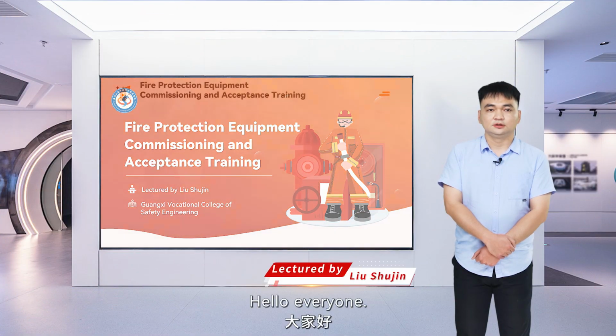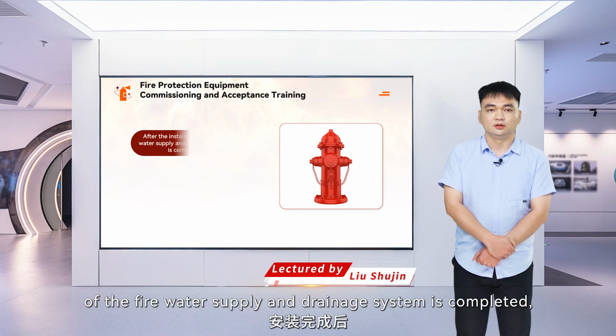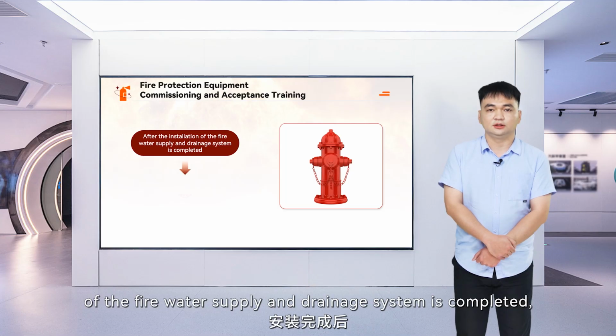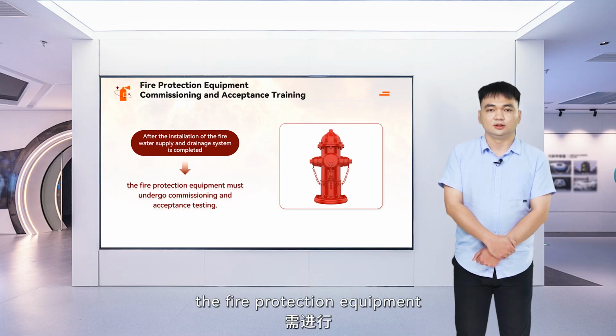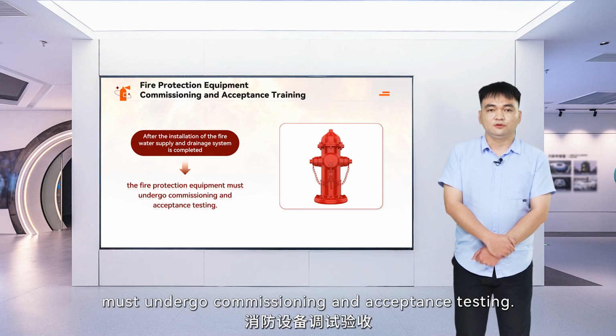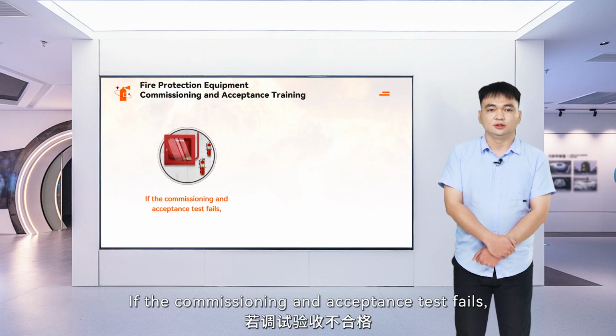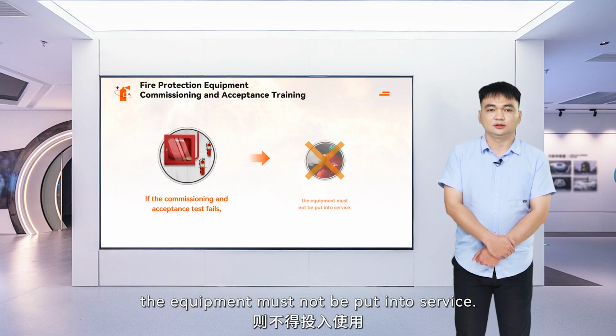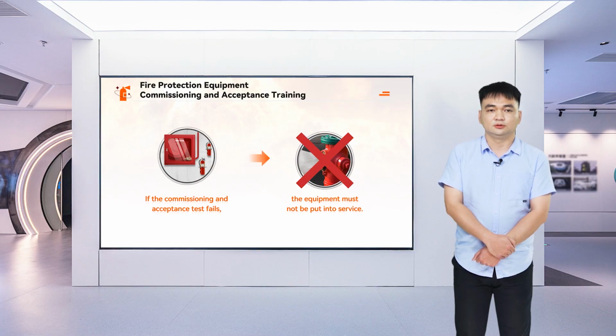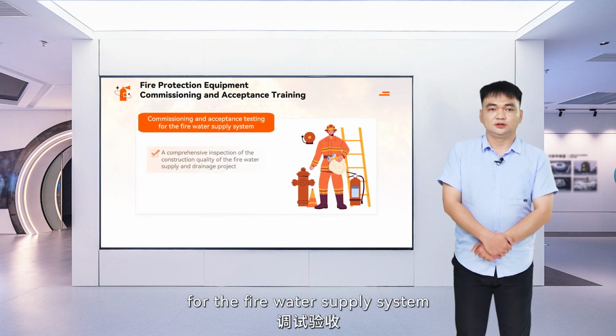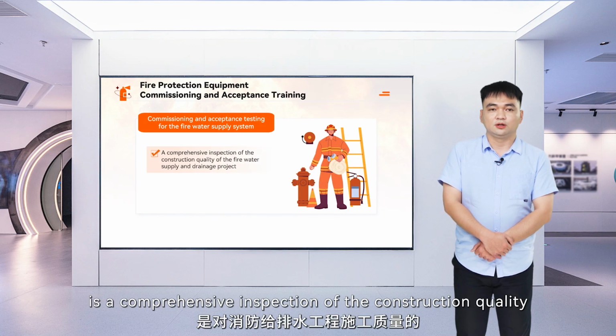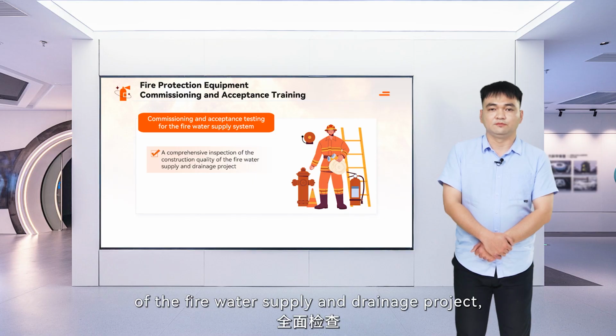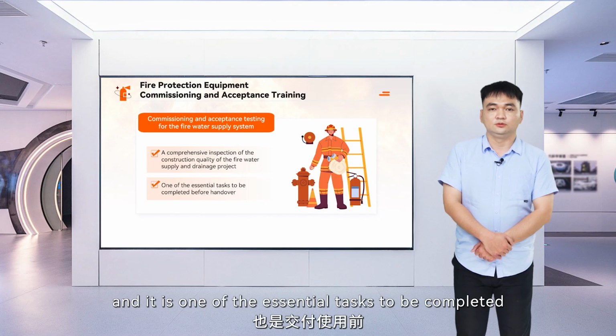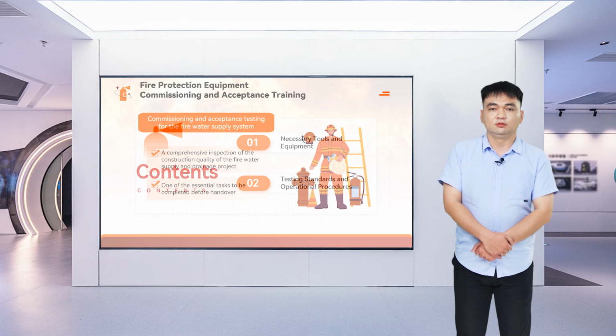Hello everyone. Usually, after the installation of the fire water supply and drainage system is completed, the fire protection equipment must undergo commissioning and acceptance testing. If the commissioning and acceptance test fails, the equipment must not be put into service. Commissioning and acceptance testing for the fire water supply system is a comprehensive inspection of the construction quality of the fire water supply and drainage project. And it is one of the essential tasks to be completed before handover. Now, let us begin this lesson.